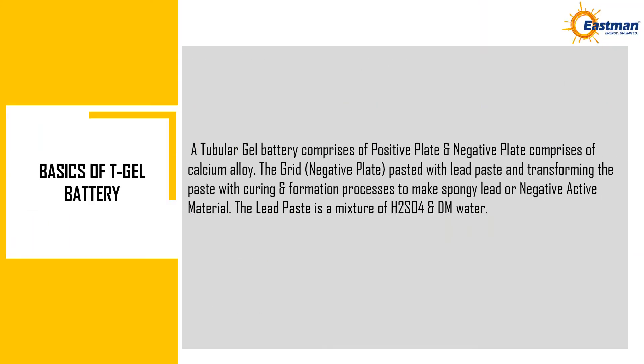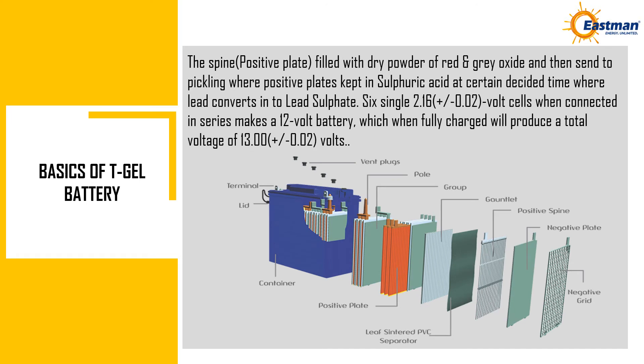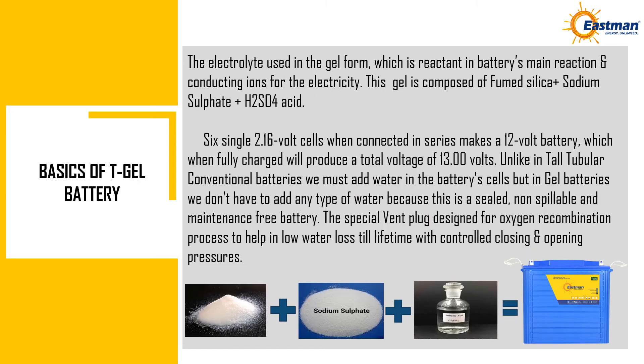Basics of Tubular Gel Battery. A tubular gel battery comprises a positive plate and a negative plate made of calcium alloy. The negative plate grid is pasted with lead paste and transformed through curing and formation processes to make spongy lead (negative active material). The lead paste is a mixture of sulfuric acid and demineralized water. The positive plate spine is filled with dry powder of red and gray oxide, then sent to pickling where positive plates are kept in sulfuric acid for a set time, converting lead into lead sulfate. Six single cells of 2.16 ± 0.02 volts connected in series make a 12 volt battery, which when fully charged produces a total voltage of 13.00 ± 0.02 volts. The electrolyte is used in gel form, acting as a reactant in the battery's main reaction and conducting ions for electricity.